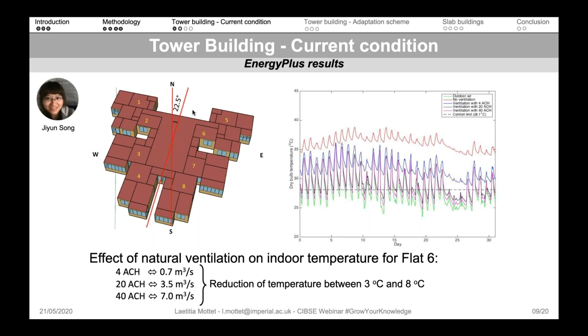Now let's look at the outdoor temperature, the green line, where you can see some spikes at the bottom of the plot. The outdoor temperature is between 25 and 30 degrees, something like 5 to 10 degrees lower than the indoor temperature. So we thought, why not use the outdoor temperature to reduce the indoor temperature and make people comfortable? Dr. Song did an exercise to increase the ventilation rate into this flat to see if we could reduce the indoor temperature. These are the other lines on the plot: blue, red, violet, and black. If we increase the ventilation rate in this tower, we can definitely decrease the indoor temperature, making people feel comfortable and use less air conditioning during hot summer.